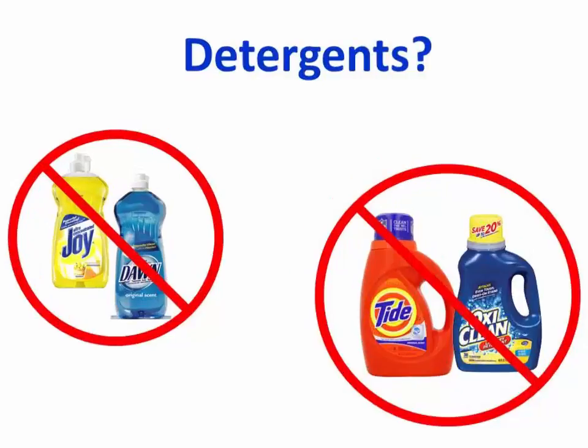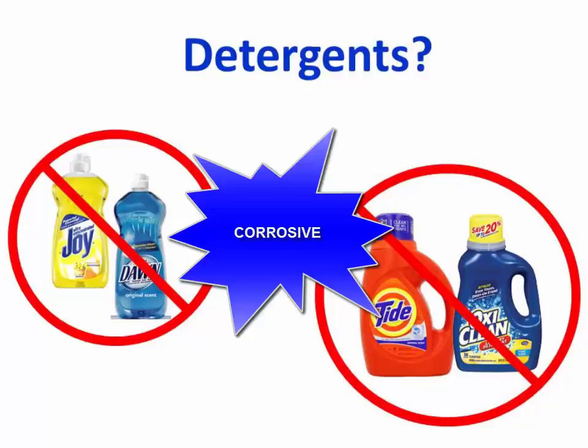Many coil cleaners are referred to as detergents, but do not confuse this with dishwashing detergents or laundry detergents. Never use those types of detergents on your HVAC equipment, as most have chemicals in them that are corrosive to metals. The aluminum, copper, and metal alloys used in the manufacturing of fins and tubing can be quite sensitive and must be cleaned with a safe, non-acid cleaner.